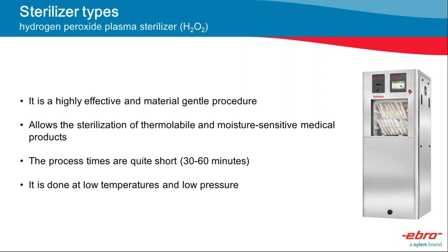Aside from temperature, you need relative humidity loggers to validate ethylene oxide sterilization machineries. Now, how can the software, the Ebro WinLog validation software, or the WinLog Med software in the medical, help you with your validation procedures? It can help you a lot because it's so straightforward to help you with your evaluations for your sterilization cycles.